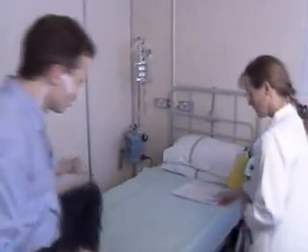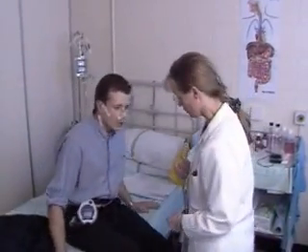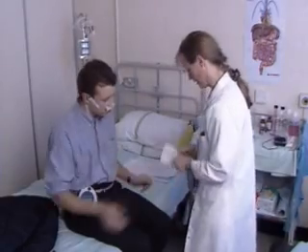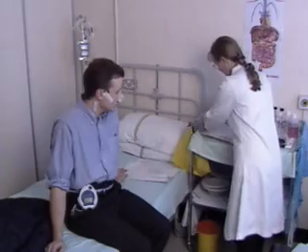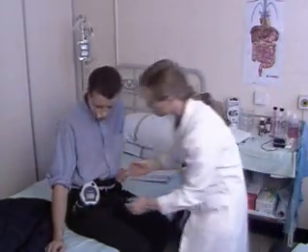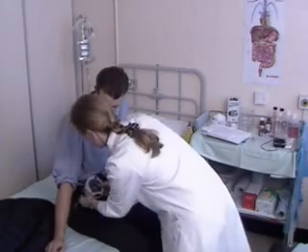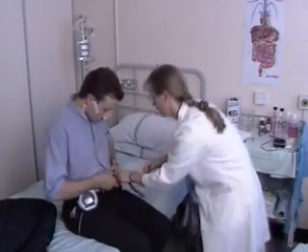The following day, the patient returns to the department for removal of the catheter. The Digitrapper is checked to make sure it is still working and recording accurate values. If the predefined protocol time has already expired, the unit will be switched off. Stop the recording, and remove the catheter with care. After the patient's diary sheet is checked, the procedure is ended.